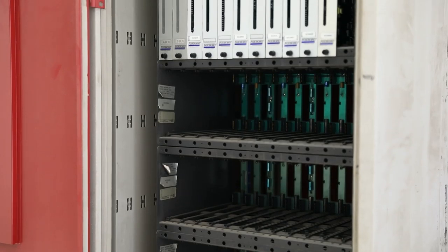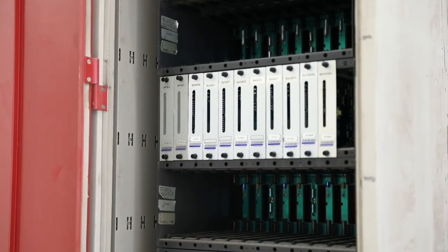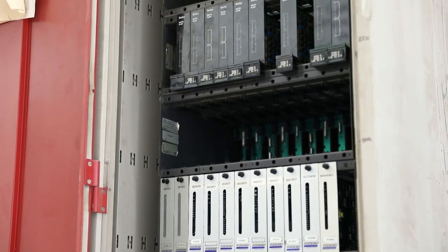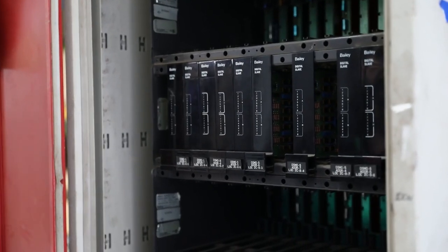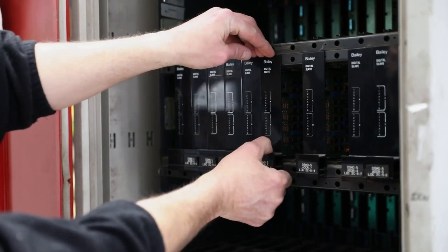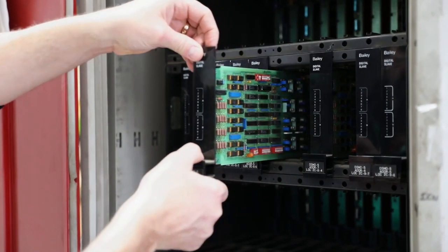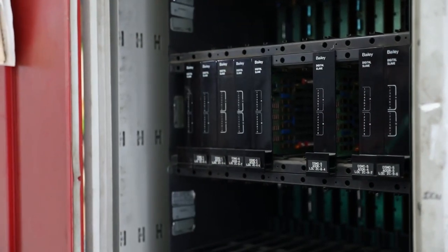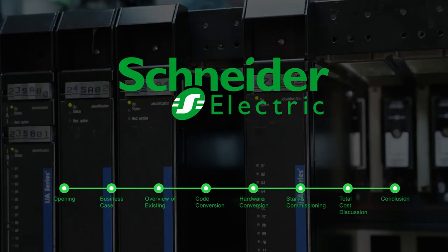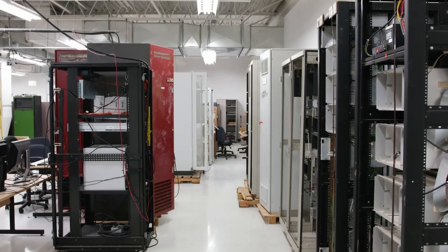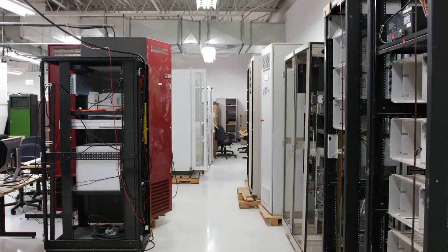We can now load up the application programs into new controllers and staged migration modules for full factory acceptance testing. The procedure includes performance measurements, stress testing, along with human-machine interface functional testing. We're almost there. Now it's time to do the swap. The hardware conversion process begins with choosing a location for your new controllers.